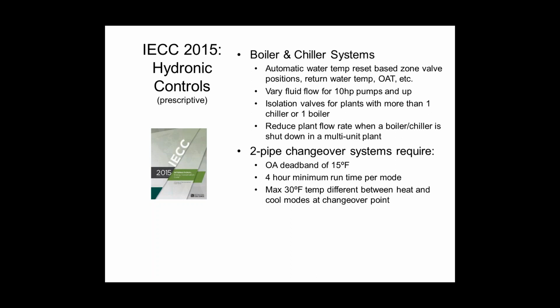You don't have to pick 60 and 75. You could pick 58 and 73 or whatever numbers you want, but 15 is a deadband, and that's a pretty big number. There's some other rules as well. Once you pick a mode, boiler or chiller, you have to run it for at least 4 hours before you're allowed to switch over to the other one. And you have to wait for the fluid temperature of the loop to cool down on its own before you switch between. And you've got to let it cool down to within 30 degrees of the set point of the other mode that you want. So there's lots of rules that make it a little bit harder to do two-pipe systems, and it'll probably result in more occupant complaints than you already get on two-pipe systems. But if you want to do a two-pipe system, that's the rules.